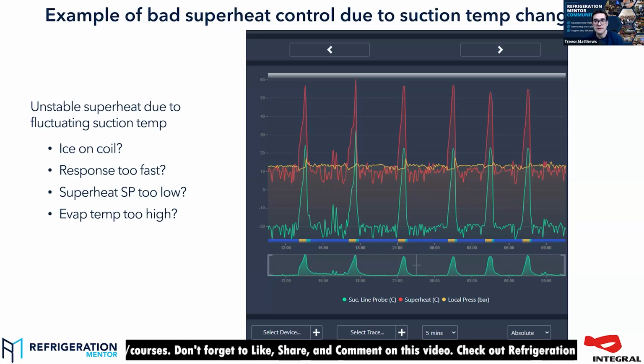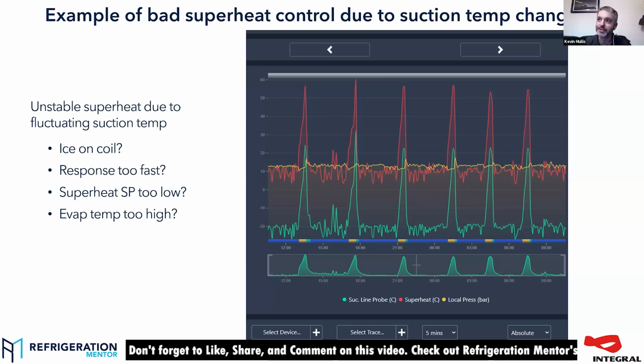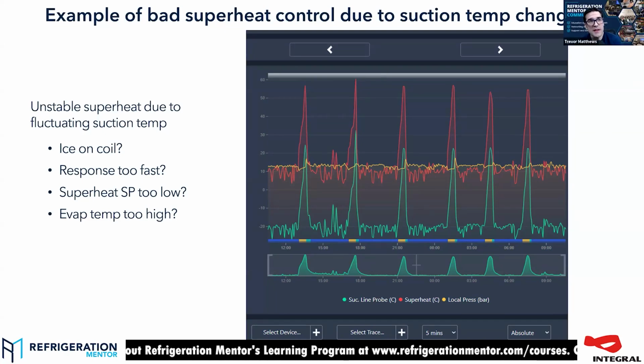If you've got a slightly more exotic system that's designed for low superheat, then you've got more opportunity to use it. But the system will take that into account, and it will have a means of dealing with overfeed. They're not so common on supermarkets. Yeah, well, I've seen more and more of them. The thing too, though, is if you set up the alarms, that will close the valve off, and you'd get an alarm for low superheat if you enable it. But once again, it comes back to programming, setting it up and understanding that controller. So, absolutely, and we could do loads on all that.